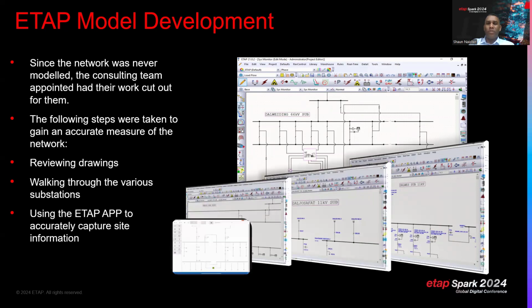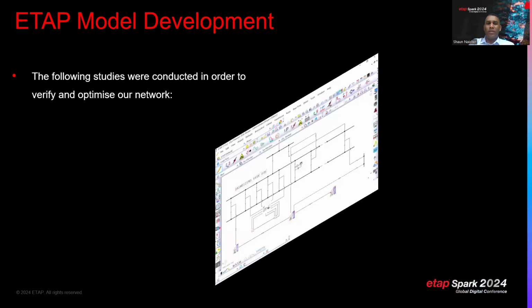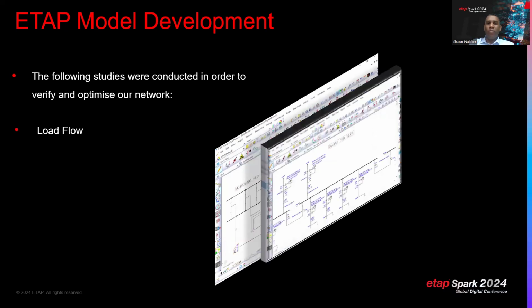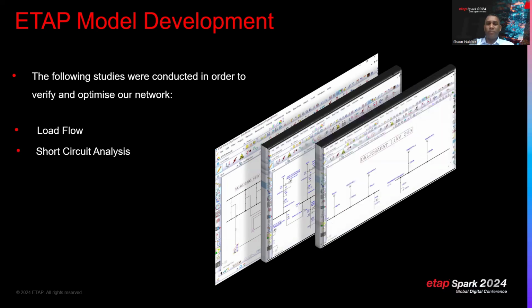Once the models were built, all data was entered in. The following studies were conducted in order to verify and optimize our network. We've performed load flow analysis to look at the power flows throughout the network to see the steady state operation of the network to ensure everything's running within its limits, able to see if there's overloads on cables and transformers, and to optimize our network.